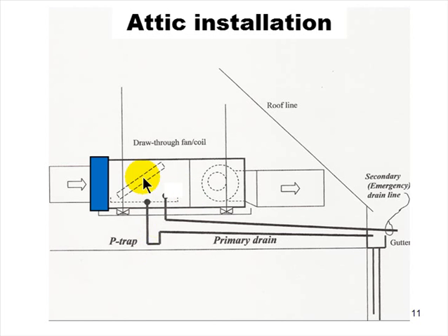starts up, this pan is on the negative side of the blower. The point of greatest negative pressure in the entire system is right there. Look how far away you are from that. You're closer to that than the duct system is. All right. So if this unit is running and you don't have a water trap in here, you have a line like this, this thing is going to suck just like this. It's going to suck air because there's no trap in here.